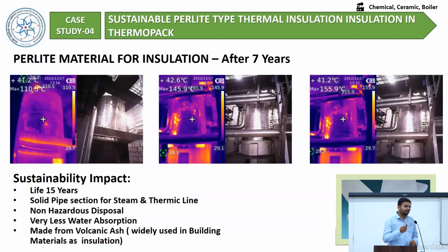The image below is the thermal image of the insulation, having the pipe section as well as the square section, and this thermal image is from after 7 years. We have seen some old applications of that insulation also. We analyzed that insulation after 7 years, and it has a 40 degree surface temperature. So it is maintaining good insulation property even after 7 years of life.